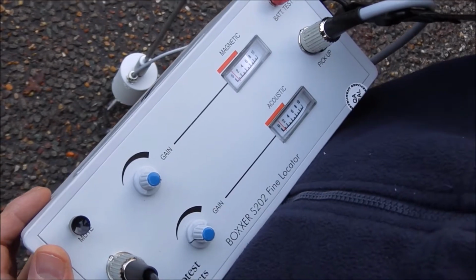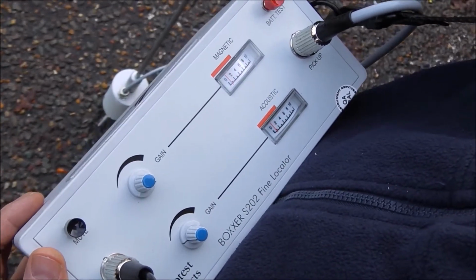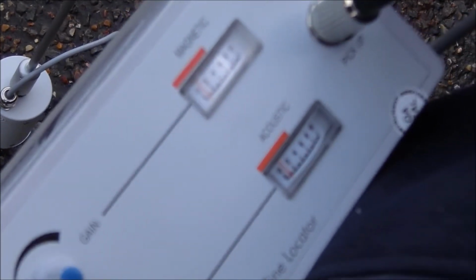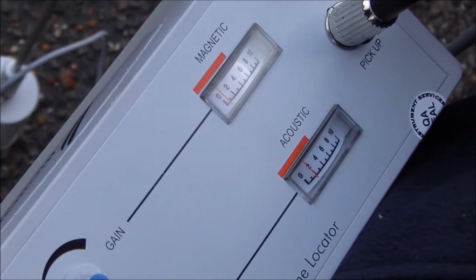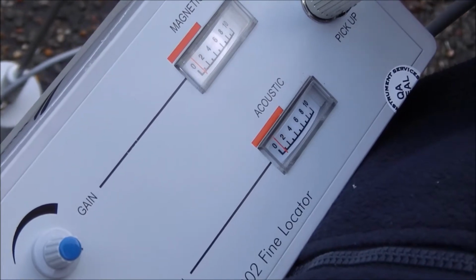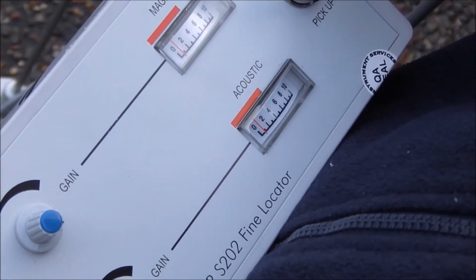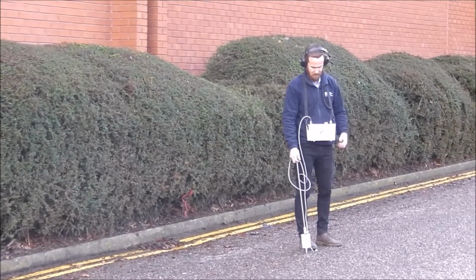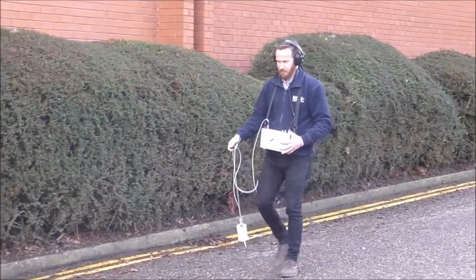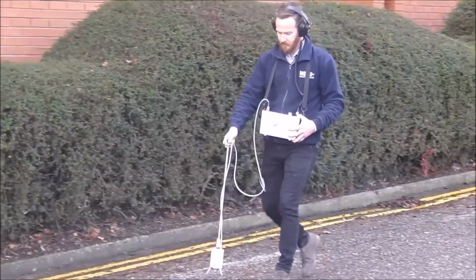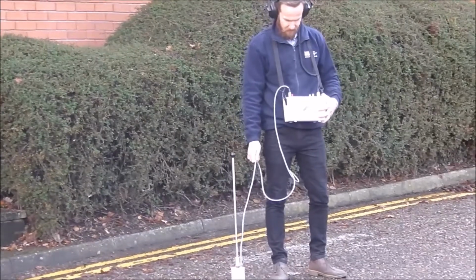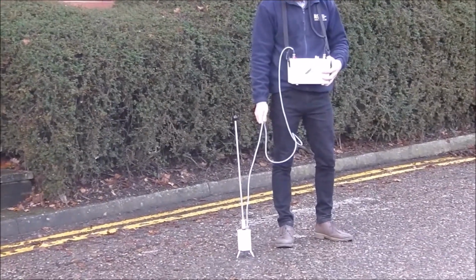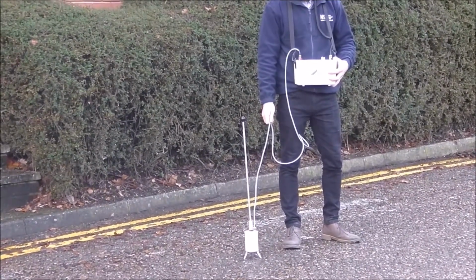Investigate the suspected fault area of the cable route with the seismophone, orientating the amplifier unit for maximum magnetic signal as already described. Vary the magnetic gain until a satisfactory deflection is obtained on the meter. By traversing the cable route and determining the position of maximum signal, the exact line of the cable may be found. The minimum sensitivity necessary to give an adequate signal should now be used in order to keep the detector over the cable.